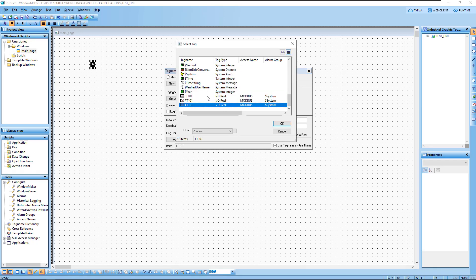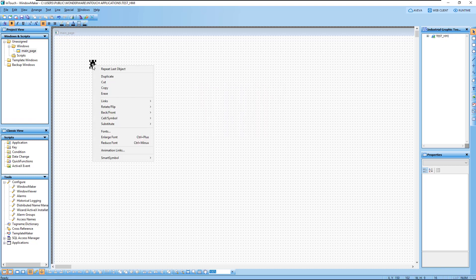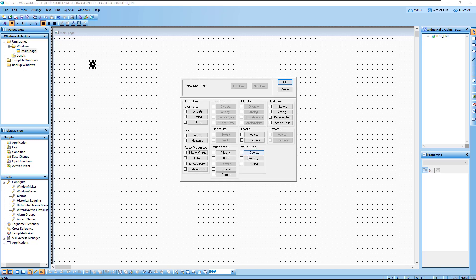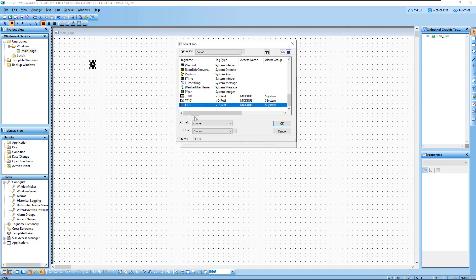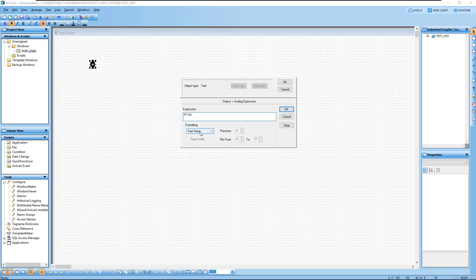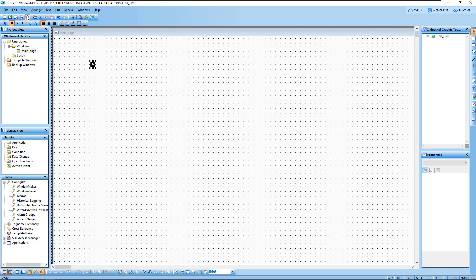If we click Select Tag, all the item tag names are already added to the system, so we don't need to define the address manually. Close this, and bind the variable to a tag name. For this analog display, double-click and look up the tag name to bind — 'PT101'. Set the format to fixed decimal with four decimal digits, then click OK and OK again. Save all.